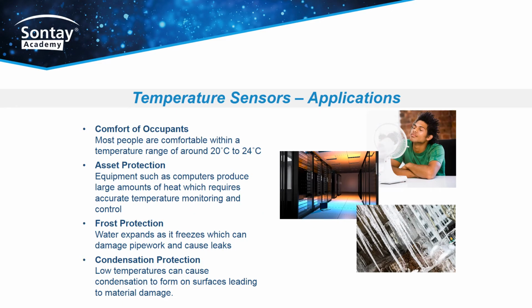Temperature sensors, applications. Comfort of occupants. Most people are comfortable within a temperature range of 20 to 24 degrees Celsius. Asset protection. Equipment such as computers produce large amounts of heat, which require accurate temperature monitoring and control. Frost protection. Water expands as it freezes, which can damage pipework and cause leaks. Condensation protection. Low temperatures can cause condensation to form on surfaces, leading to material damage.